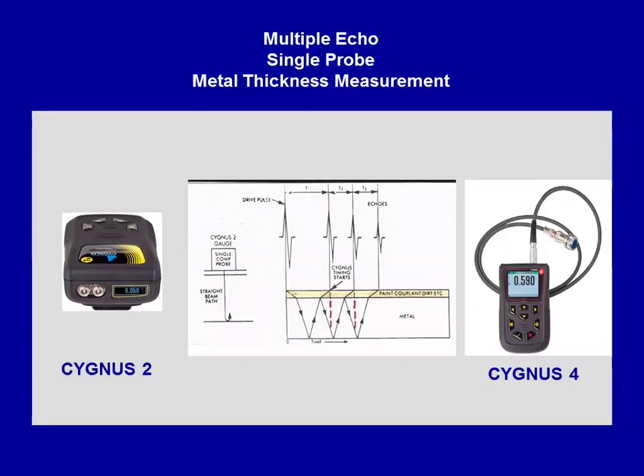Now, when you can't match the timings between the second and third echoes, and there could be a whole bunch of reasons, then the gauge says, well, wait a minute, the timings didn't match. Let's say you had severe pitting or something on the other side, and the sound is going down, ricocheting and bouncing around. What happens with our gauge when we can't match the timings between the second and third echoes is it goes blank. We'd rather piss you off and give you no information than lie to you and give you false information. So the good news with our gauges is they always give you a measurement when they should, and won't give you one when they shouldn't. That has its own set of headaches as well, because nothing is 100%.